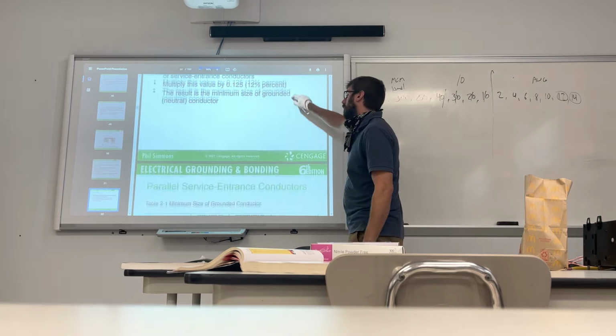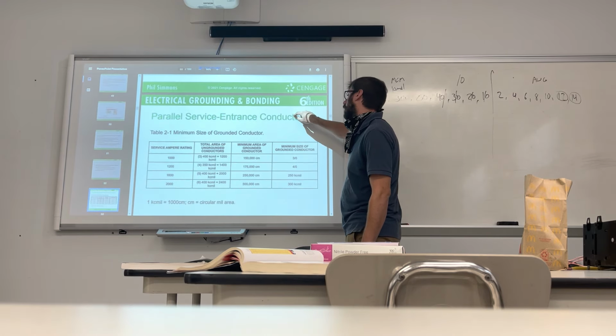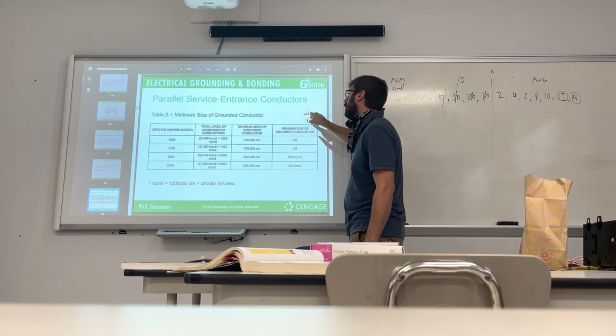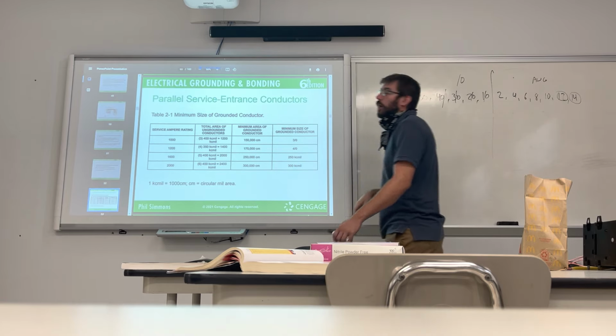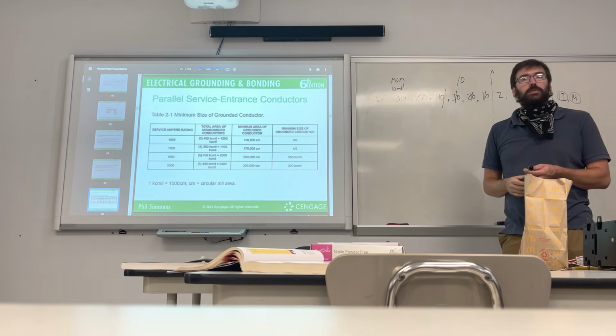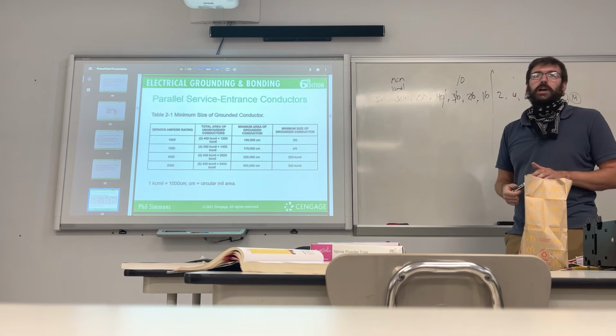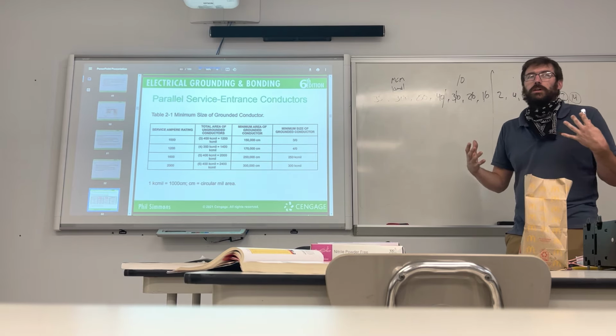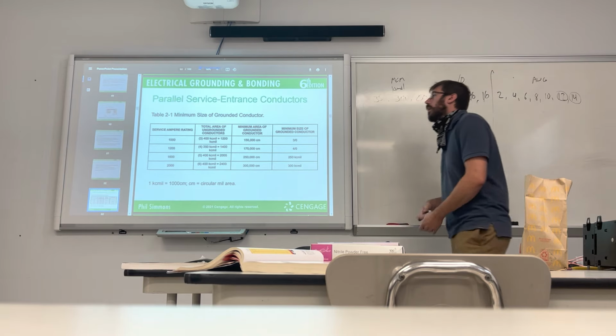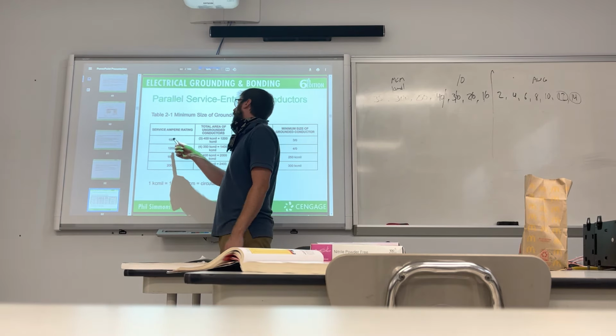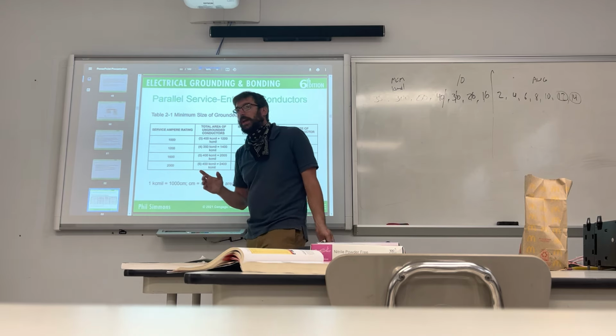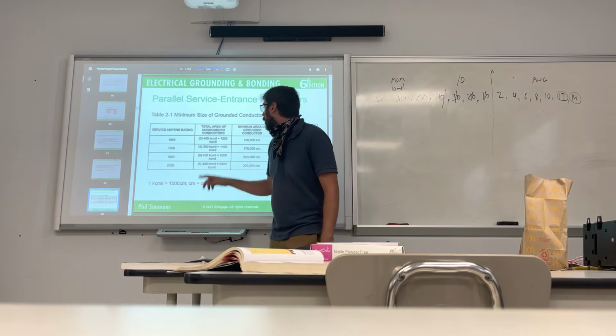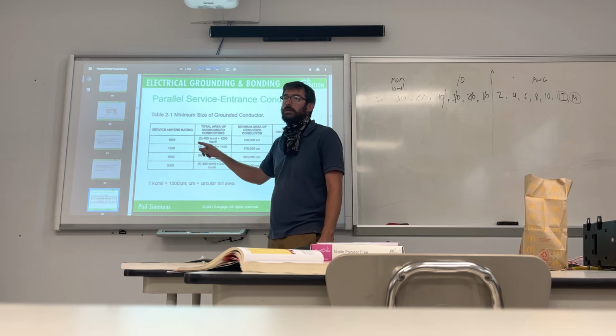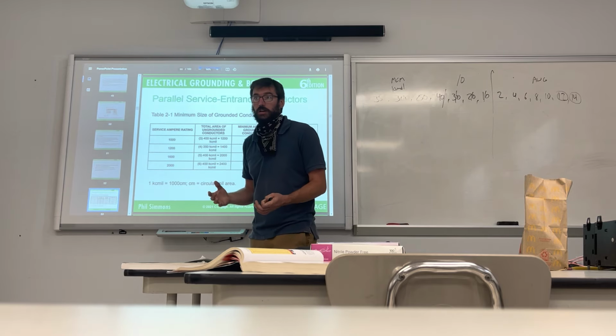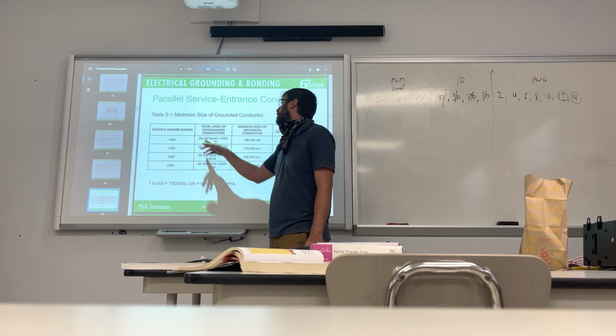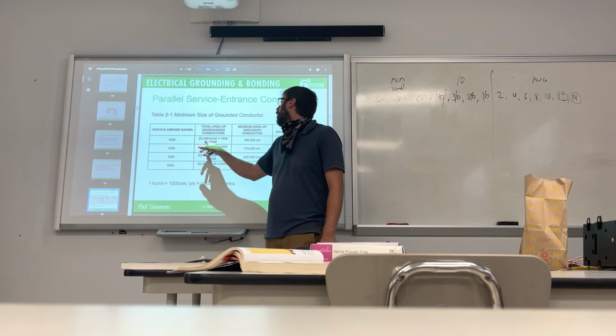Now here, let me just see what this next has to offer. Oh yeah, this is great. Perfect. I was really hoping they would show this. Good. All right, so at a certain point we will start paralleling up wires to double up our power availability. What do I mean by that? So you've got a service rating of 1,000 amps. So they ran three 400 kcmil lines for each leg. Let's say there's three legs. So there's nine of these wires coming in, but they're all bunched up.